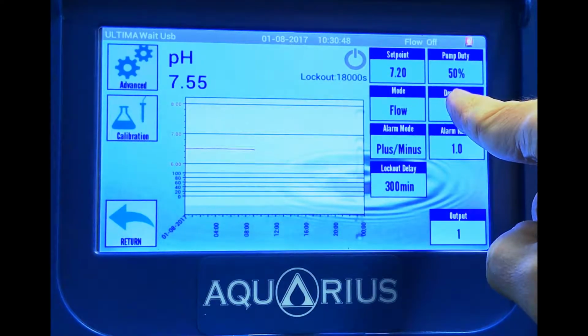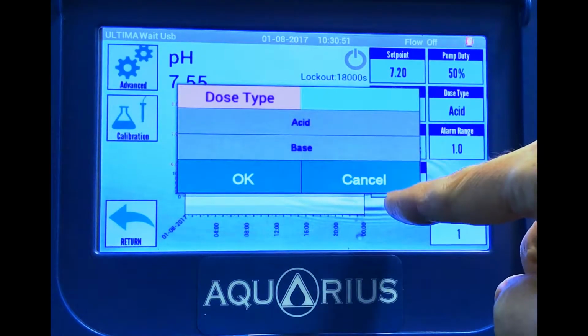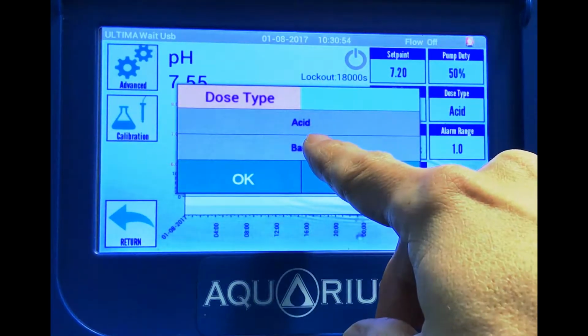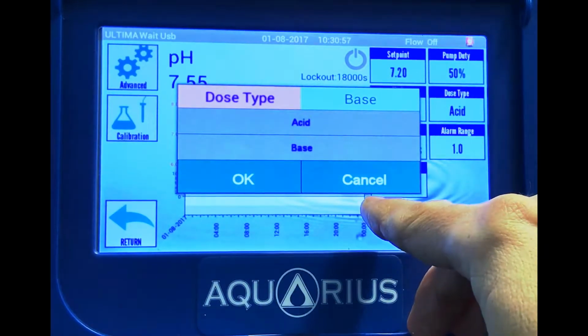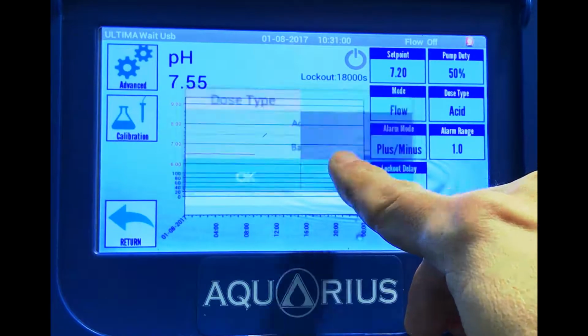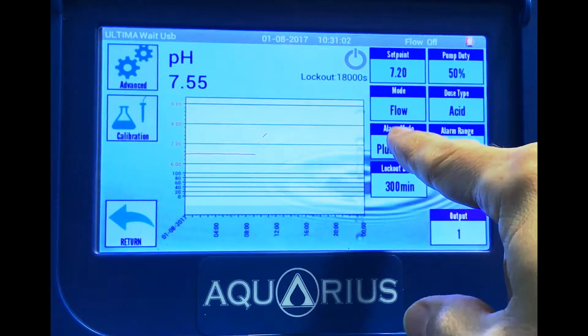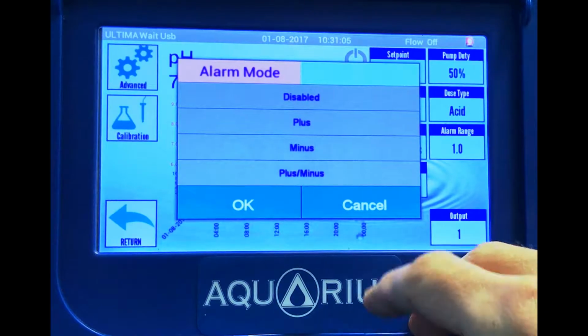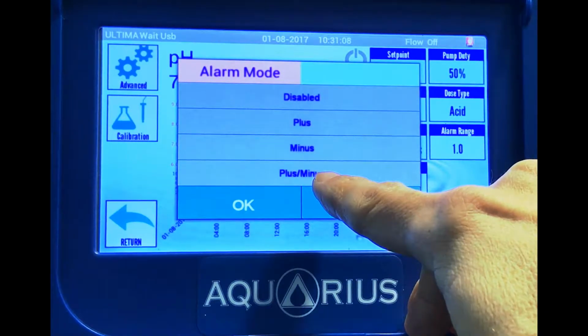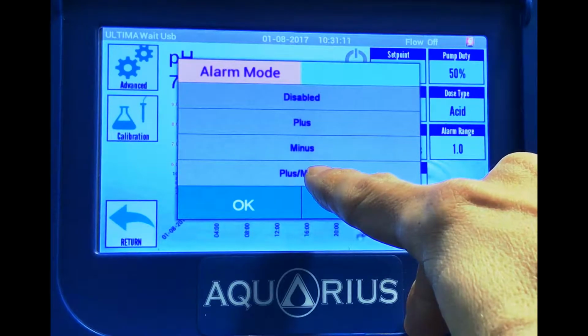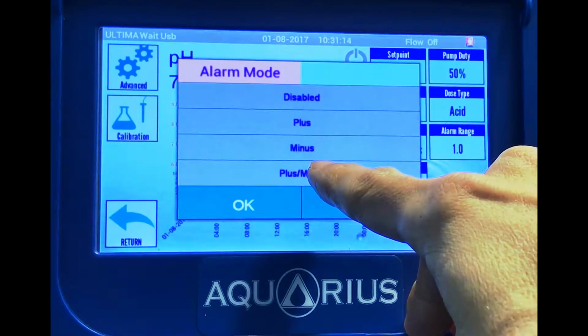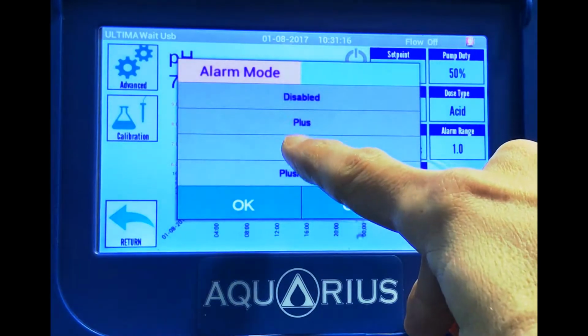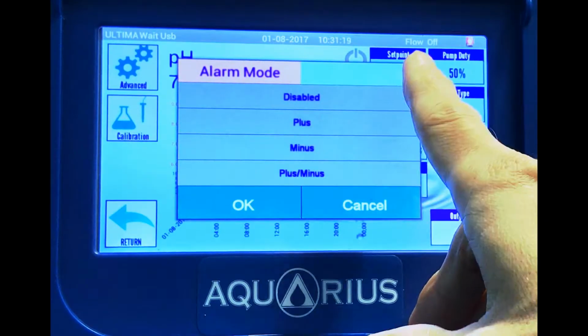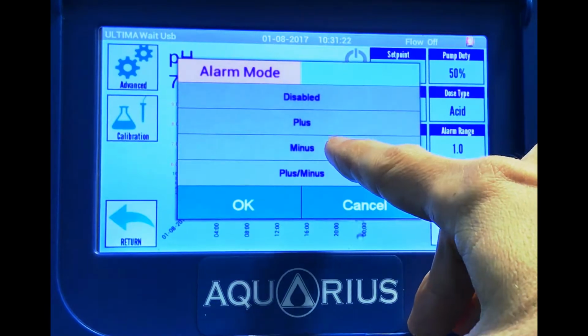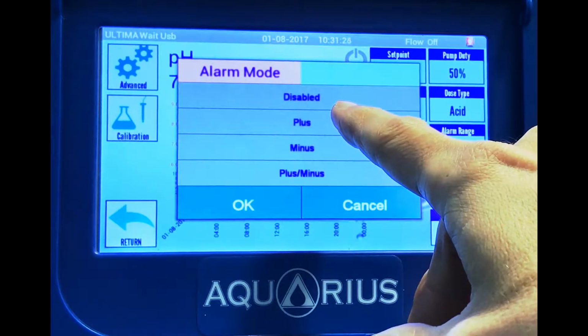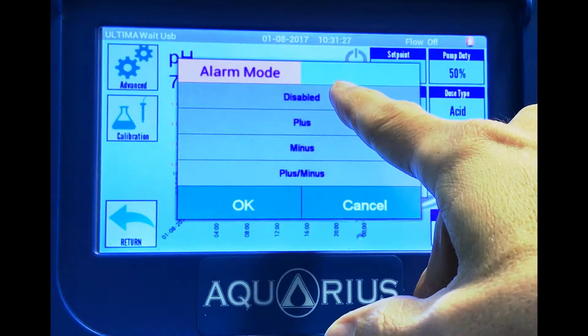Dose type is set for acid, so it would only dose above the set point. Setting it for base, it would dose below the set point. Alarm mode, plus or minus. So the alarm mode gives you an option to send or receive an alert if the pH reading is either above or below the set point, and then you have options for only below or only above or disabled completely.